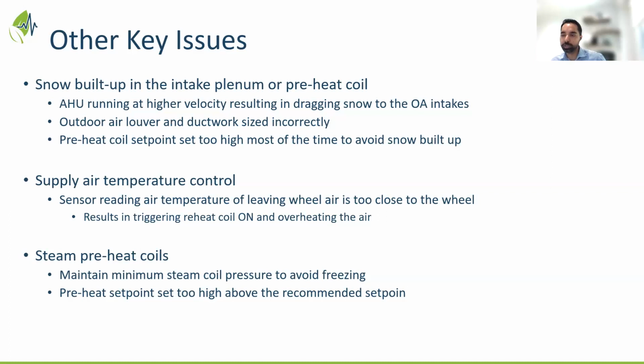It is a control issue, but it's related to where the sensors are placed, what they are being used for, how they are calibrated, and whether you are using an average value across the sensors to bring on your heating coil. So this is an issue where it's a big system and the sensors are not accurately placed where they should be. A lot of the lessons learned are about the placement of the sensors, how they're being used, and what type of sensors should be used in the facility. So this could probably apply to many of the facilities across different provinces.